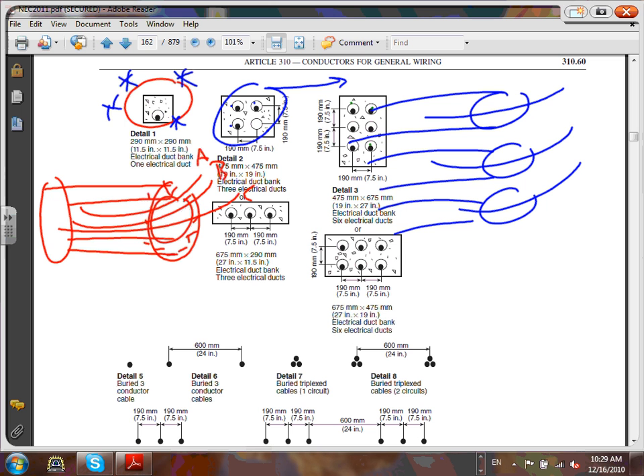I mean, 3 of these, the one I have in my office, I can guarantee you can cover 1/3 of the city of Minneapolis with power. You can put them in 3 conductors like I have in my office. They're running at 115,000 volt, and each one of them is 2,500 kcm. 3 of them for the 3-phase. You covered 1/3 of the city of Minneapolis. So it's a huge power you can get out of these.